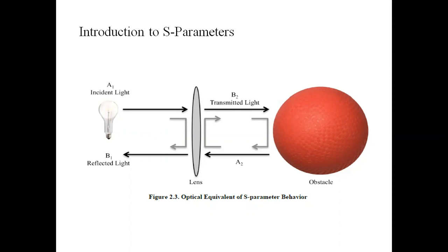Today, scattering matrix results such as S21, for example, are displayed on the VNA display screen with a simple push button. Moreover, the instrument is able to apply the appropriate calibration techniques to remove a wide range of inherent impairments of the instrument itself. And in order to better understand these parameters in an intuitive way, it is useful to first consider an example.